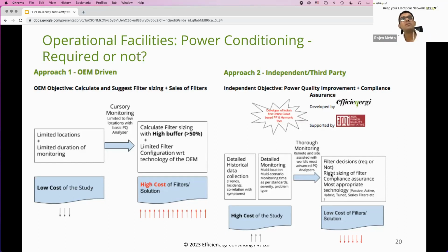Then the question becomes whether or not a filter is required. That's the first thing to determine. If a filter is needed, what can be done with your existing reactive power compensation or filtering already in place? That's the approach we want people to take, but more often the easier path is chosen, where just the OEM is asked to do the study, two or three other quotations are invited, and the study is done that way. As a result, the cost of the solution you end up going for is very high.